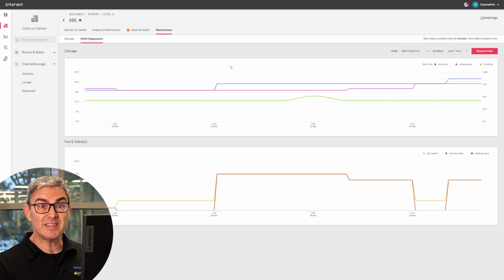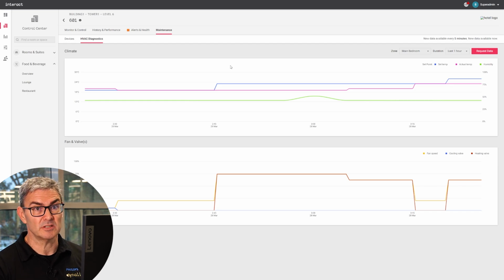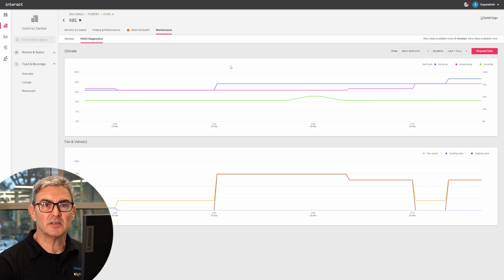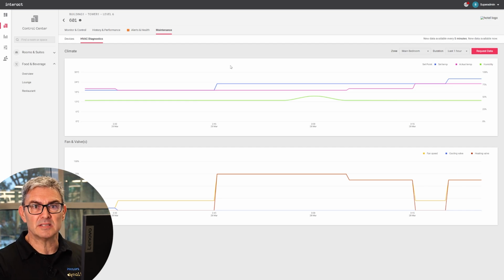As the function operates behind the scenes, these valve and fan speed settings have not been exposed prior to now in the hospitality dashboard. This is not an issue when everything's operating as expected, but should there be a customer concern with the room HVAC performance, it's important that the facilities team can see exactly what's happening in order to troubleshoot the system. So to support this, we've extended our current climate graph feature and added fan and valve output data to the existing temperature and humidity information. So facilities teams can now use this data to validate the system's operation and quickly diagnose an issue, such as a stuck valve or a filter that needs cleaning.